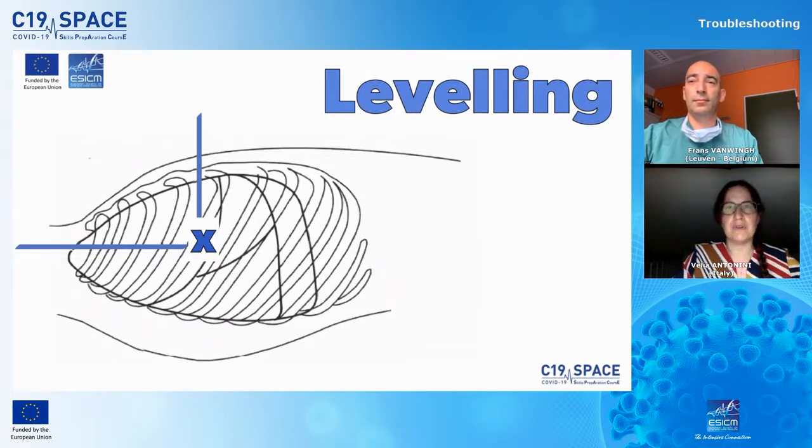Leveling is so important. Not being rigorous in proper leveling introduces error. For each centimeter of offset, you have 1.36 millimeters of mercury of error. If the transducer is too high, pressure is underestimated. If the transducer is too low, pressure is overestimated. And this mostly impacts low values such as CVP or severe hypotension. Check and fix the level every time you move the patient, every time you move the bed, and every time you have any kind of doubt.